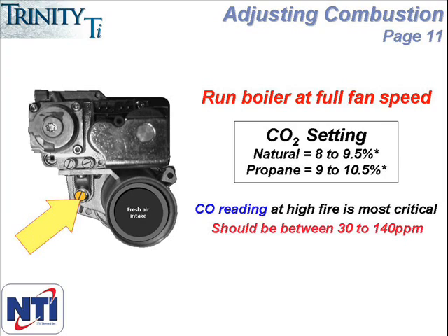The CO readings should be less than at high fire, and the CO2 readings should be at least as high as at high fire, but shouldn't exceed 9.5% for natural gas or 10.5% for propane.